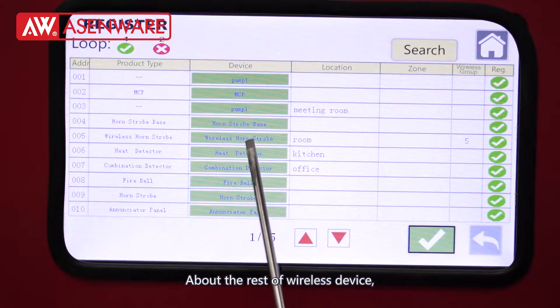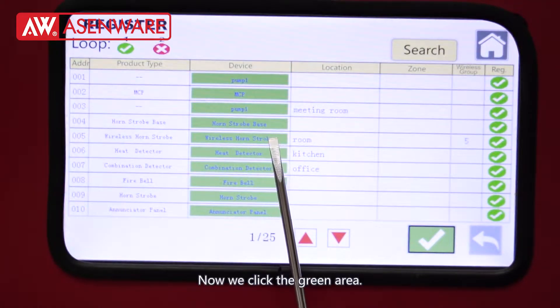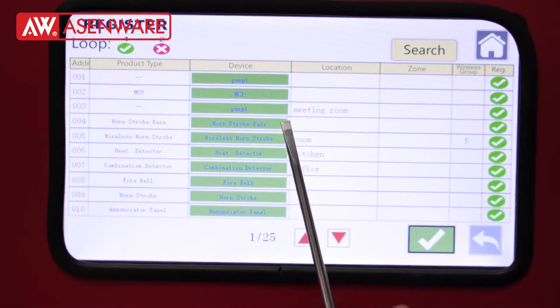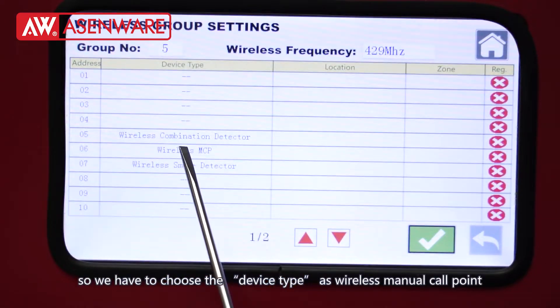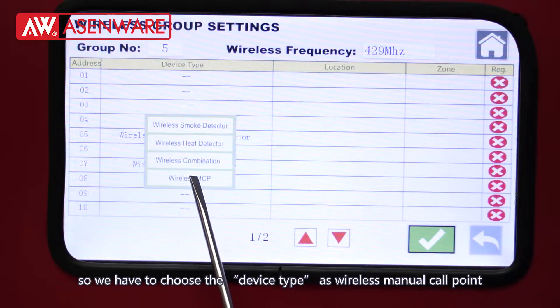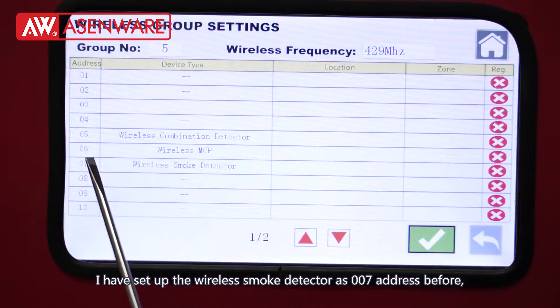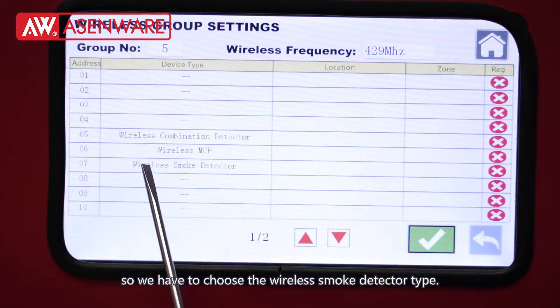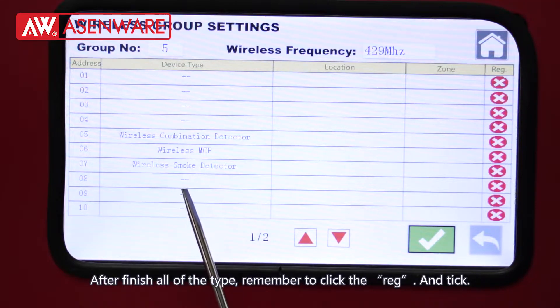For the rest of the wireless devices, we have to manually set up the address. Click the green area. I have set up the wireless manual call point as address 06, so choose the device type as wireless manual call point. I have set up the wireless smoke detector as address 07, so choose the wireless smoke detector type. After finishing all of the types, remember to click the register and check.